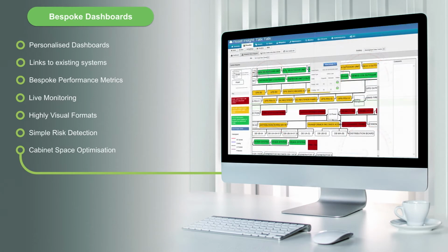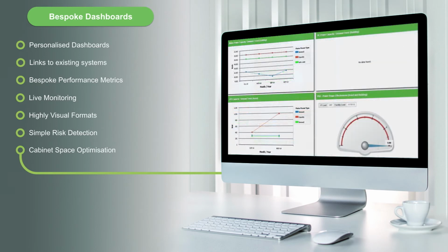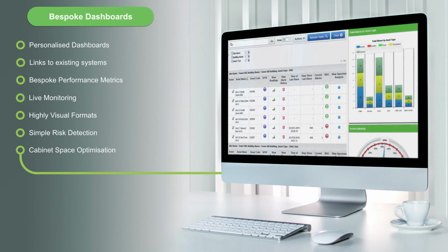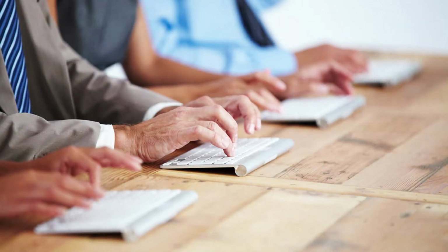For example, reliability block diagrams plot each individual system and asset in a building, measuring the power, cooling capacity and demand of each asset before storing it within the system. This information is then used to detect single point of failure (SPOF) locations using a traffic light key so engineers can identify and resolve issues before there's any impact on the business.